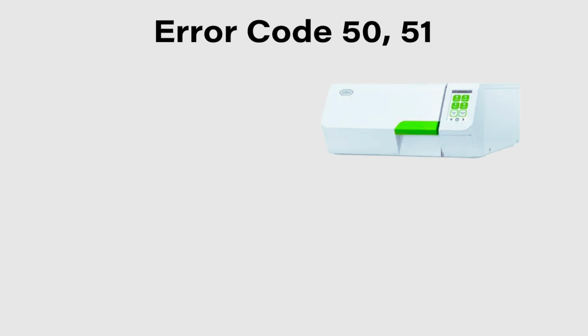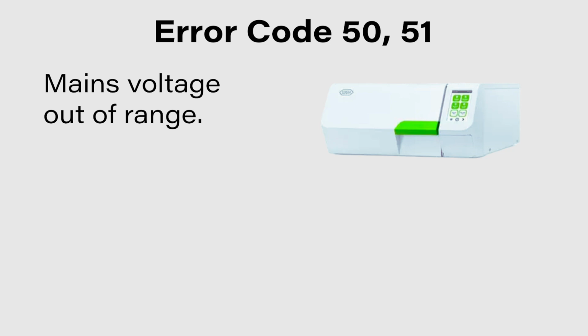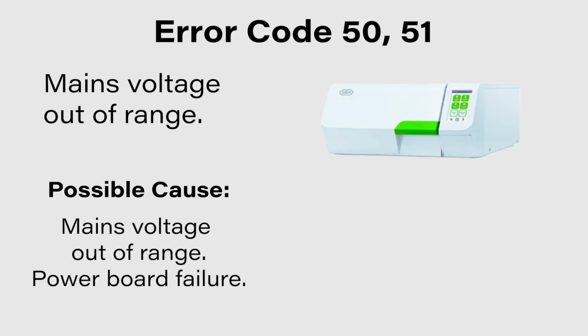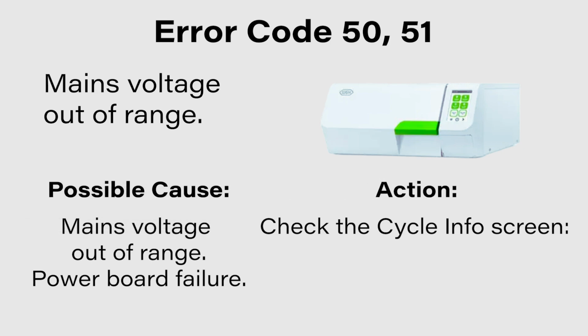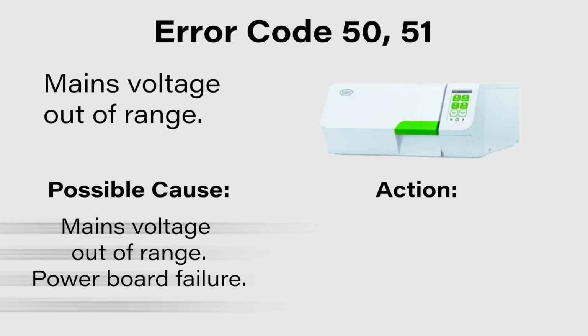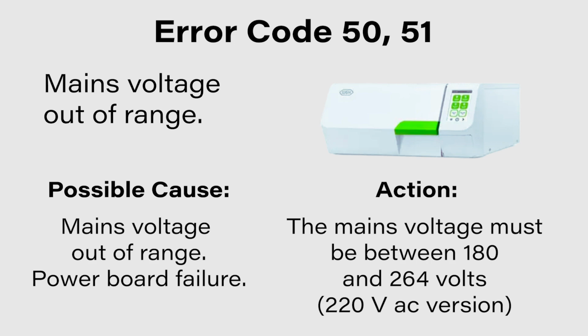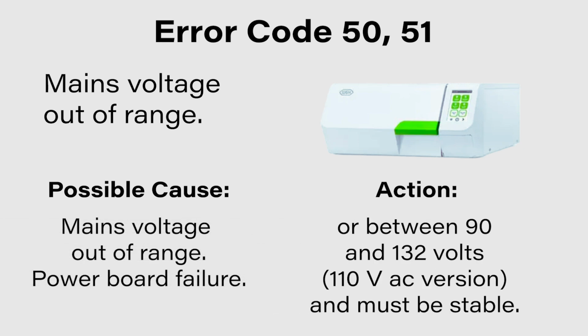If your W&H Lexa Mini Autoclave is displaying an error code 50 or an error code 51, that means that the mains voltage is out of range. The possible causes could be the mains voltage is out of range or a power board failure. For this, check the cycle info screen. The mains voltage must be between 180 and 264 volts for the 220 volt AC version, or between 90 and 132 volts for the 110 volt AC version, and must be stable.